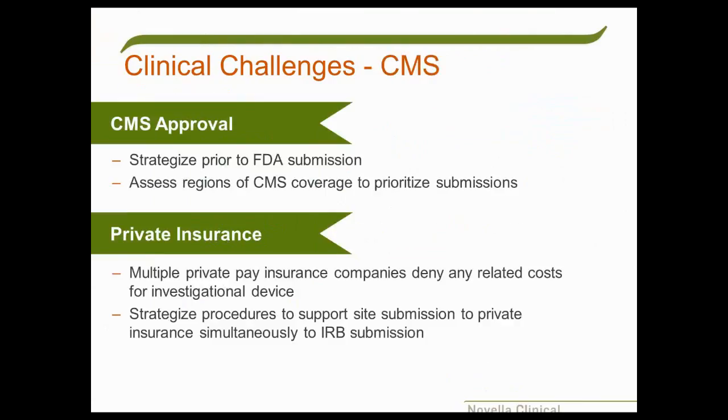CMS, I'm going to touch on this briefly because it is kind of purely a medical device aspect, but if you're going to try to get CMS reimbursement during the trial, you need to plan for that far in advance. The approvals take a significant amount of time. For those of you who have done this, you're familiar with this timeline, the complexity of it. And once you get national approval, then you need to go to each state, get approval there, understand what their submission process and approval process is.